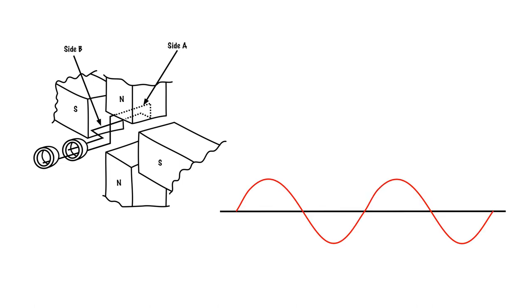So here we go. If I go north to south, that would be this hump on the sine wave. South to north would be the bottom side. North to south, I go up and over. And south to north again, underneath, and I get two full sine waves. So with a four-pole alternator, 360 mechanical degrees gives me two complete sine waves. So we can start seeing if we add more poles in here, we end up with more sine waves which gives us more frequency.